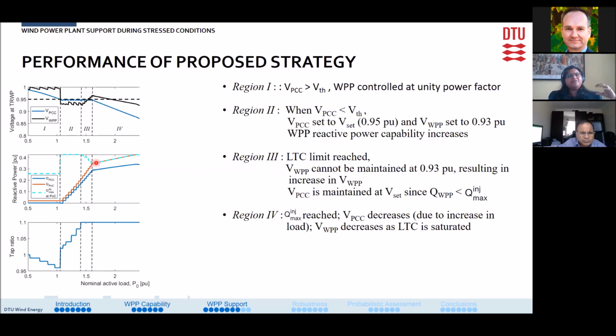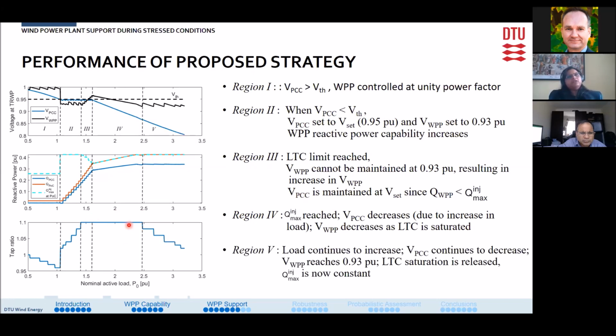The reactive power capability limit of the wind power plant is reached, as seen here. As a result, VPCC can no longer be maintained, and it starts decreasing due to the increase in load. Consequently, the wind power plant voltage also starts to decrease. However, we see that the tap changing transformer is still at its maximum limit. As the load further increases, the PCC voltage continues to decrease.